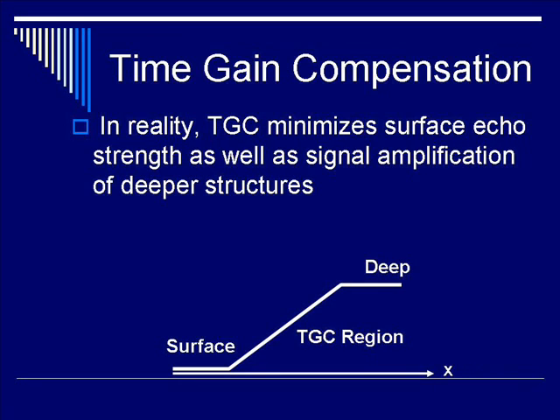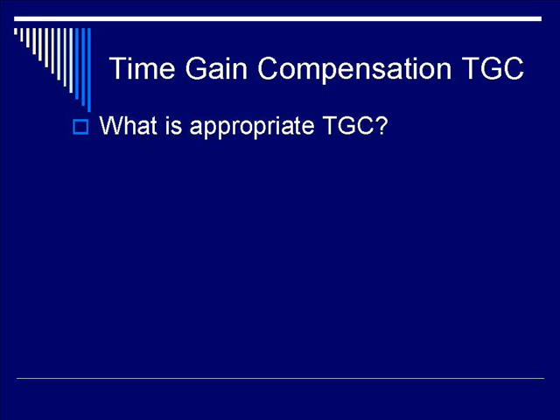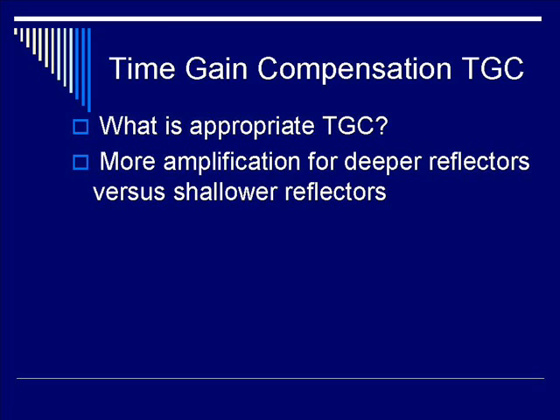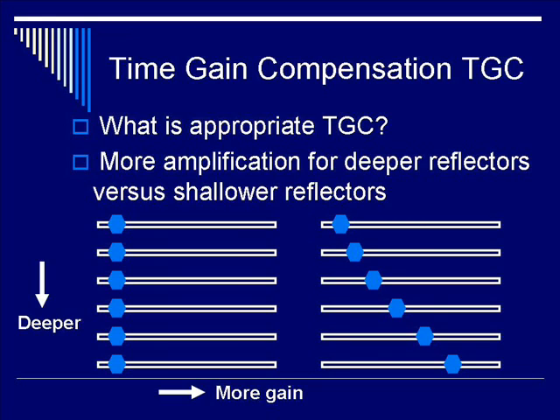At the surface and very deep in the body tissue, you do not really apply much gain. However, in between, you apply a constant slope — or a slope of your desire — that gives you the appropriate TGC compensation. Note that TGC is under operator control. In terms of the TGC slider bar seen on some machines, the vertical scale is depth — as you go down, you get deeper — and the horizontal scale is gain, where going to the right gives more gain. For a soft tissue situation, you want to turn up the gain for the deeper structures.